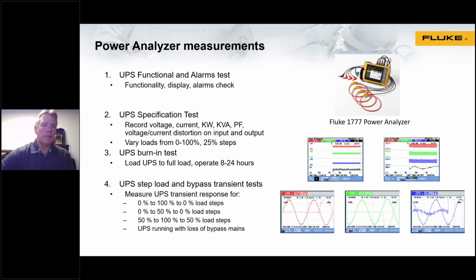So initially, the first test literally is just a UPS functional alarms test, looking for proper display values, making sure that you don't have any alarm messages. The tests after this, I believe there's 8 different tests. We'll be using a power analyzer. Here's an example of a new power analyzer that we have called the Fluke 1777. So I'll be referring to this. It's a full 3-phase power analyzer that can capture all the types of measurements that we're going to be discussing.